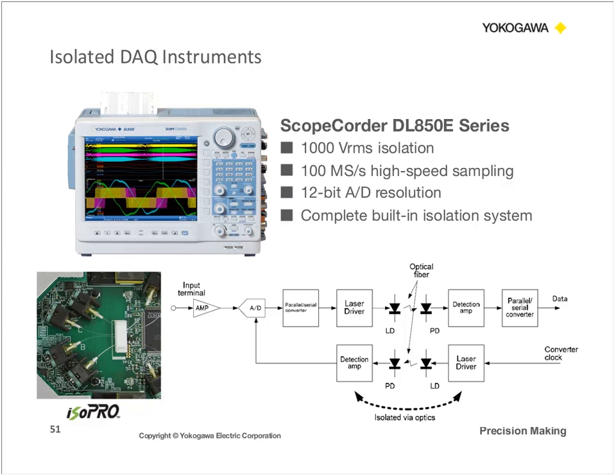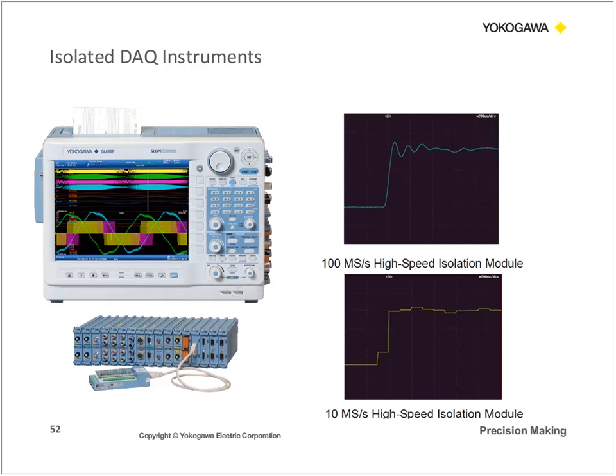It has a complete built-in isolation system, so it implements the three that we talked about, which is channel-to-channel isolation, channel-to-ground isolation, as well as module-to-module isolation. And what this means, put here as an example, let's say you're making a pulse measurement, a PWM or a VFD measurement, right? And if you're using, for example, a 10 megasample per second module, so even though that's high speed, if your signal is too fast, you're not going to be able to accurately recreate the signal. And what you end up having is this stair-stepping effect, which I'm sure most of you are familiar with. But also when you're making high voltage measurements, it's not going to be able to accurately capture that spike, maybe that you have an inrush voltage or an inrush current, and you're not going to be able to accurately detect the peak. So really you need high-speed sampling to be able to sample enough of the signal to recreate it.